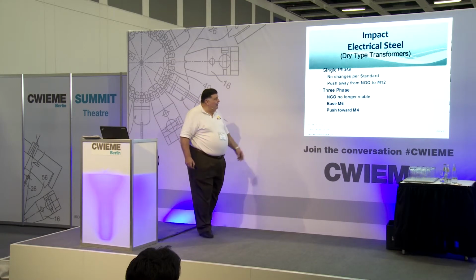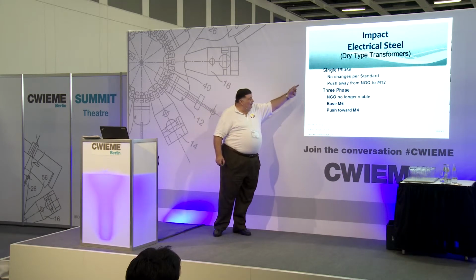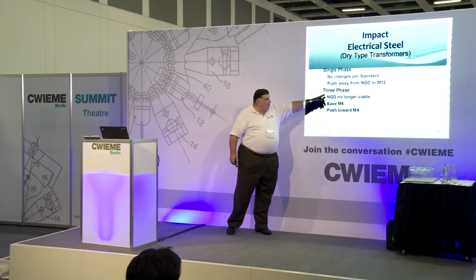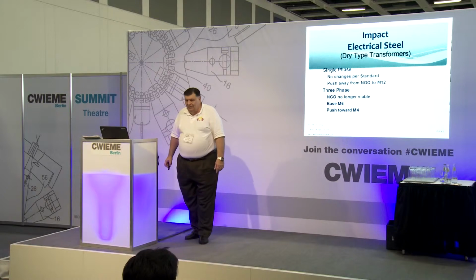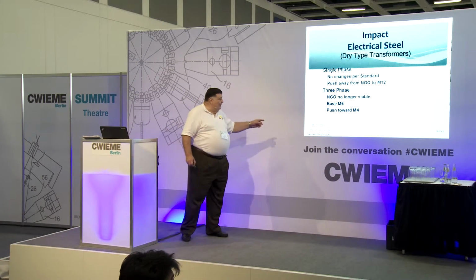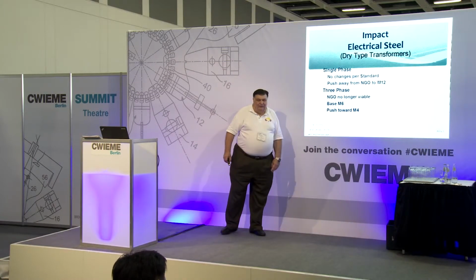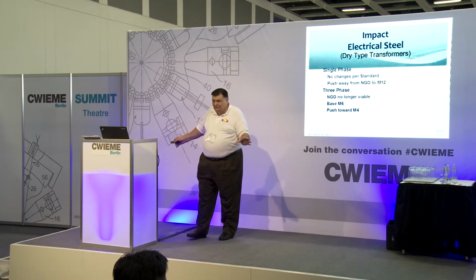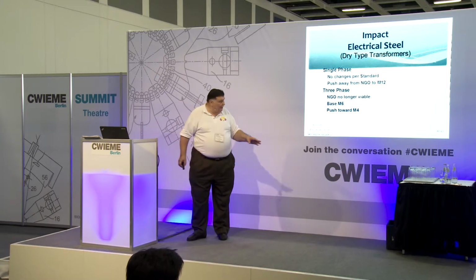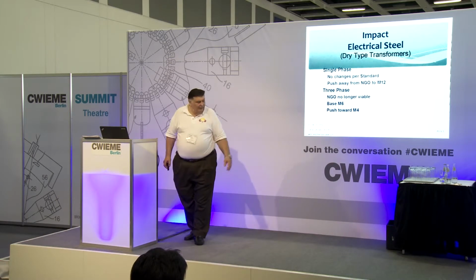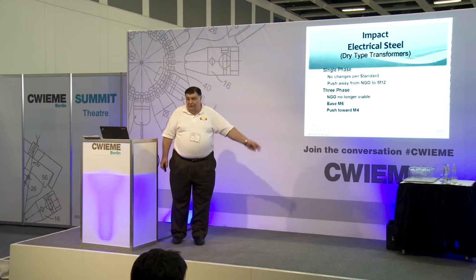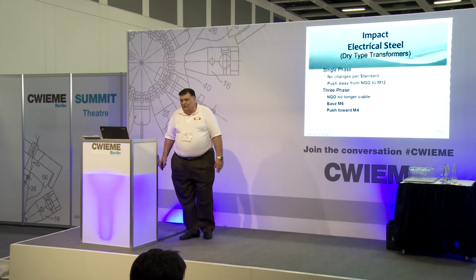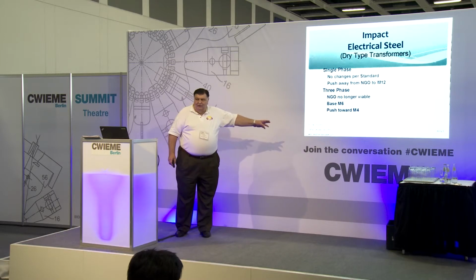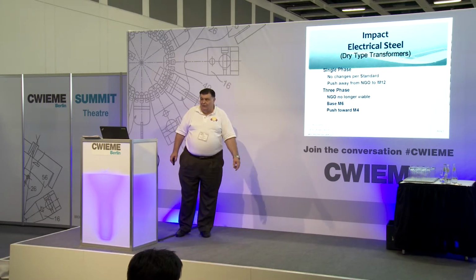Impact on electrical steel, like I said before, dry type, single phase, no change. There's going to be a push away from using non-grain oriented to using an M12 product as their base. Three phase, non-grain oriented in the United States is out. And pretty much in Japan it's out. The new base will be an M6 product. And a push toward M4, which is a major change on the dry type transformer. They go to an M4, they can keep the overall size of the transformer down.